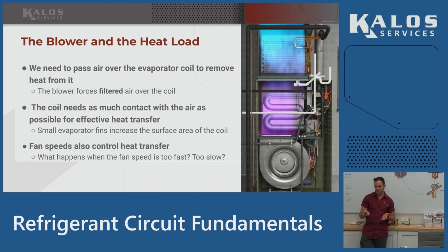I was just gonna ask, on the thing with the ECM, is that just a thermostat programming thing? No, the thermostat just tells the fan to run or not run. What's controlling that is either a board, if you have a certain kind of air handler, or the actual speed tap you put onto the motor. It'll have speed taps 1, 2, 3, 4, 5, and wherever you put your G call is where that motor will run. Oh, okay. As an installer, you're looking at what specific speed they need. Yeah, exactly. So we're trying to hit a certain CFM.